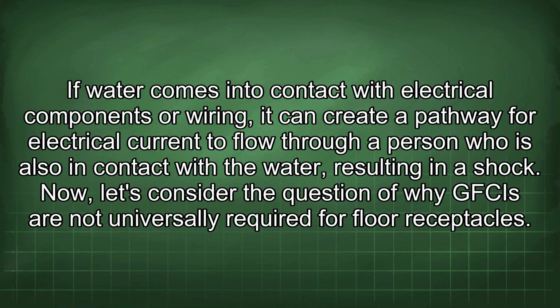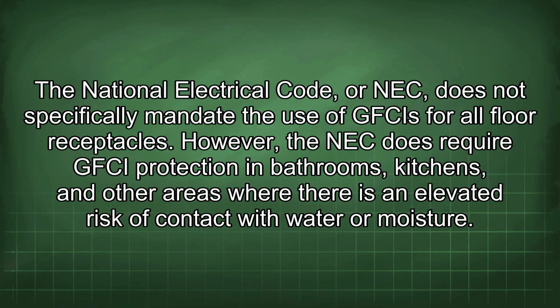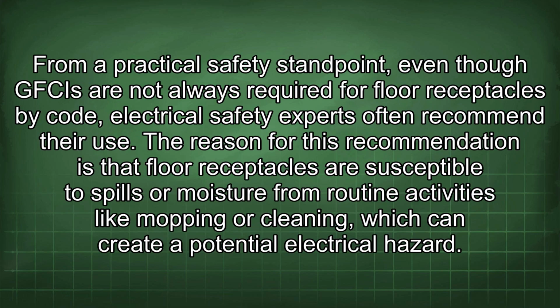Now, let's consider the question of why GFCIs are not universally required for floor receptacles. The National Electrical Code, or NEC, does not specifically mandate the use of GFCIs for all floor receptacles. However, the NEC does require GFCI protection in bathrooms, kitchens, and other areas where there is an elevated risk of contact with water or moisture. From a practical safety standpoint, even though GFCIs are not always required for floor receptacles by code, electrical safety experts often recommend their use. The reason for this recommendation is that floor receptacles are susceptible to spills or moisture from routine activities like mopping or cleaning, which can create a potential electrical hazard.